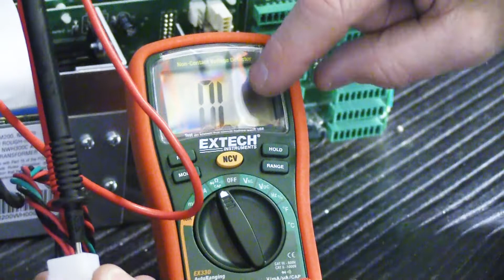So if we jam it in here, we're getting no beep and no resistance measurement on the meter. See, OL, over limit, no resistance, no beep. That's good. And then if we do 3 and 5, like this—oh look, I got them jammed in further, now they stay better—so now we're on 3 and 5, it still shows over limit and no beep, which means no continuity, which means no short in the master station.